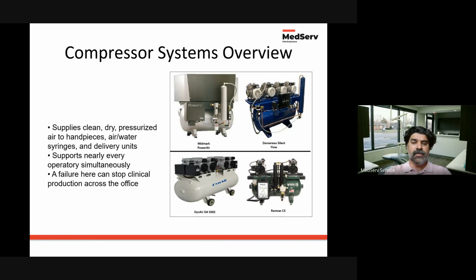And so you'll hear complaints sometimes, if these PMs aren't done regularly, that a handpiece feels weak, or the air sounds wet, or it sputters, or that the compressor itself is turning on, then off, and then on again. That sort of repetitive behavior is usually pointing you towards the issue that there's something not working on the compressor itself.